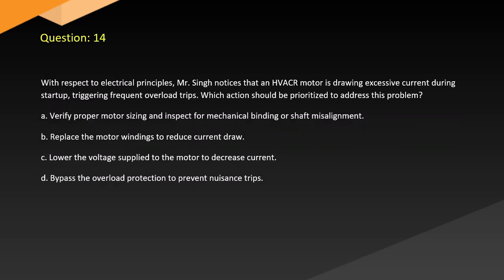Question 14. With respect to electrical principles, Mr. Singh notices that an HVACR motor is drawing excessive current during startup, triggering frequent overload trips. Which action should be prioritized to address this problem? A. Verify proper motor sizing and inspect for mechanical binding or shaft misalignment. B. Replace the motor windings to reduce current draw. C. Lower the voltage supplied to the motor to decrease current. D. Bypass the overload protection to prevent nuisance trips.